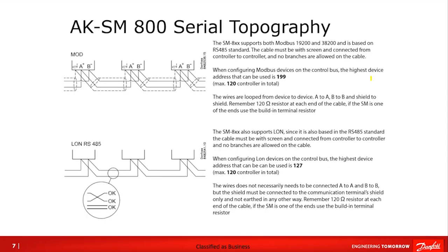The wiring layout for the SM800A. When we focus on our Modbus and Echelon plugs, these are point-to-point daisy chains — we typically have multiple devices linked together on a communication loop back to one plug. Each plug at each downstream controller connects back to the System Manager. We want to keep the integrity of that communication loop, keeping A and B consistent throughout from one device to the next. We don't want any stars or other wiring configurations — just point-to-point back to the controller.